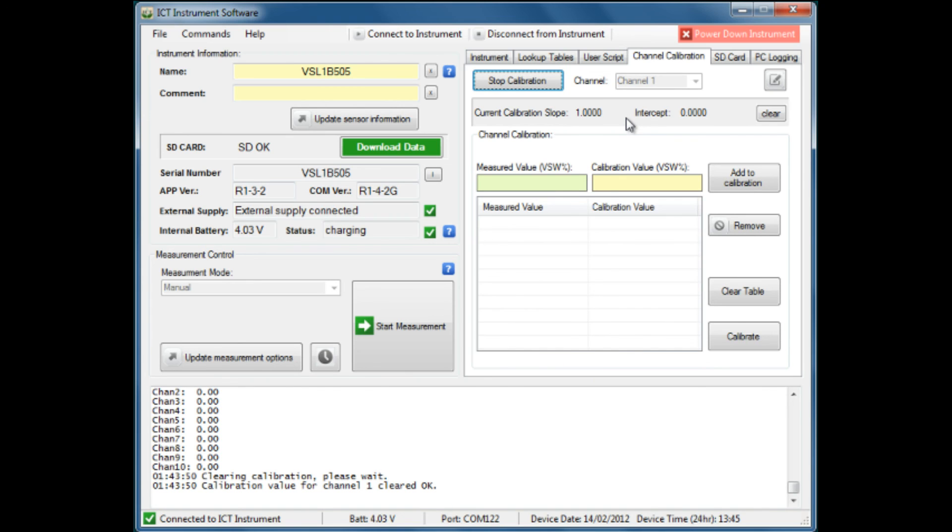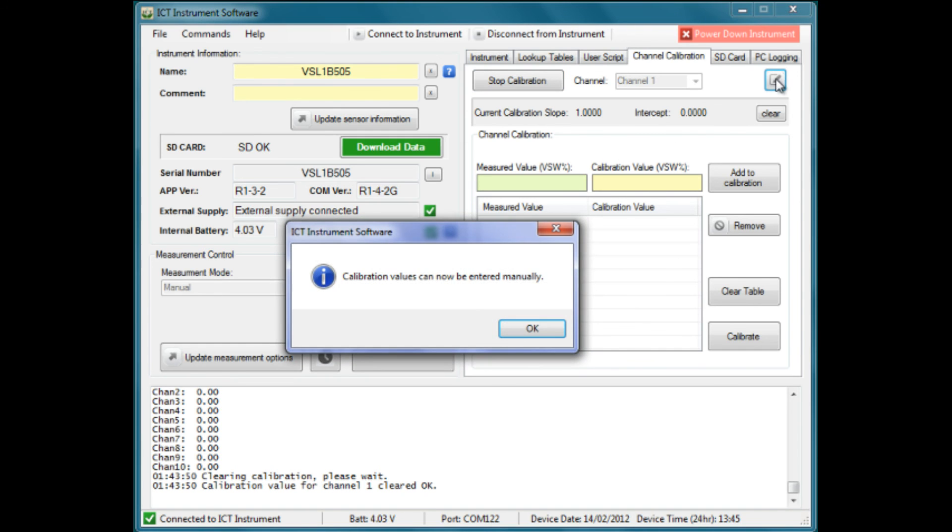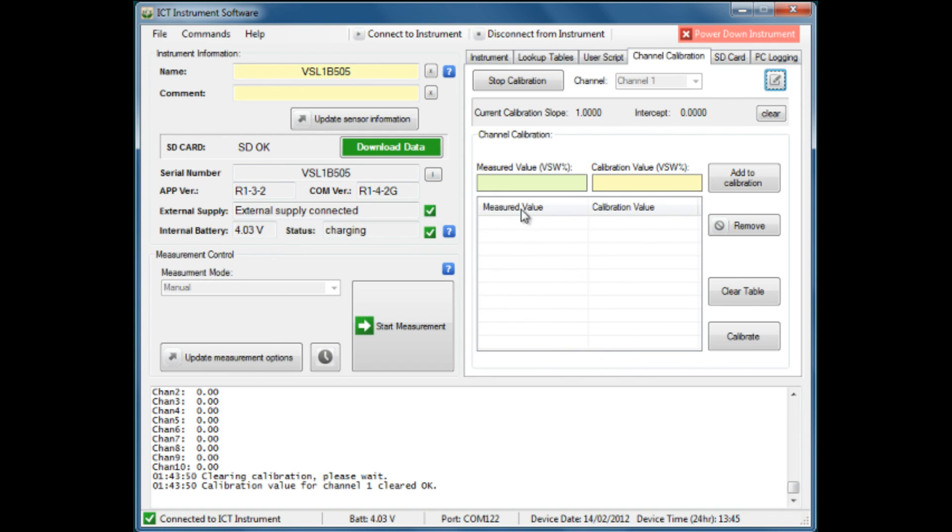For this particular sensor, we are able to use the fact that at zero moisture content it would produce zero output. We will use that as our first entry into the calibration table. We click on the little pencil icon up here and confirm that we are able to manually enter calibration values. We enter a measured value of zero and a calibration value of zero, add those to the calibration table, and that becomes our first entry.